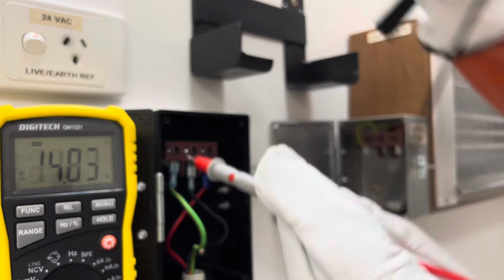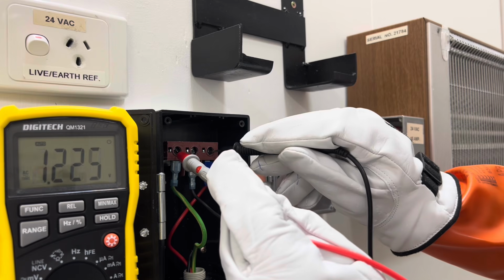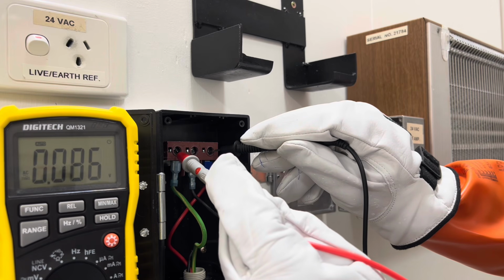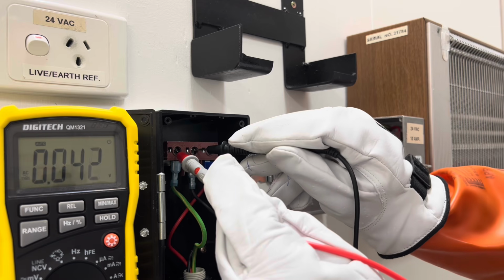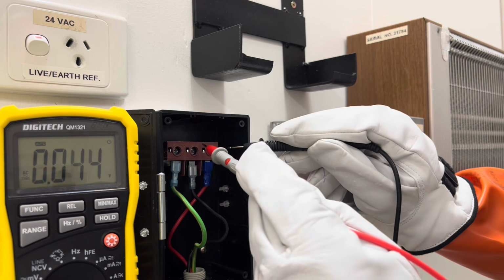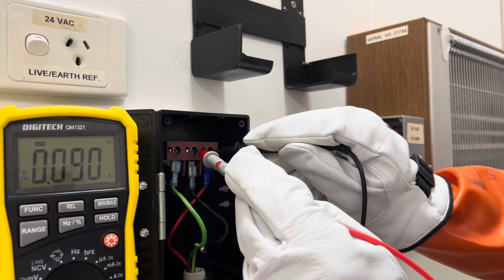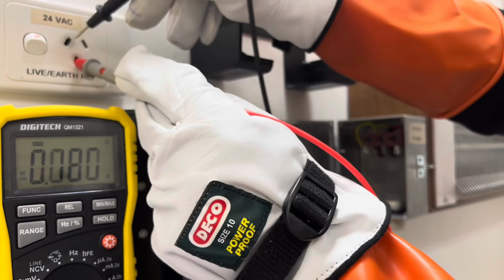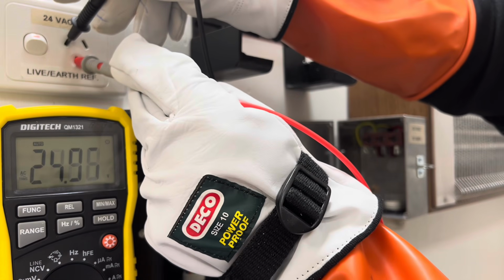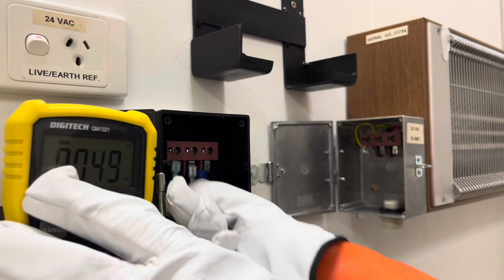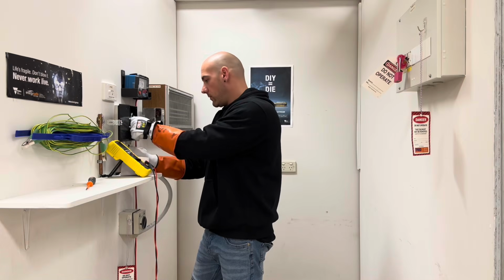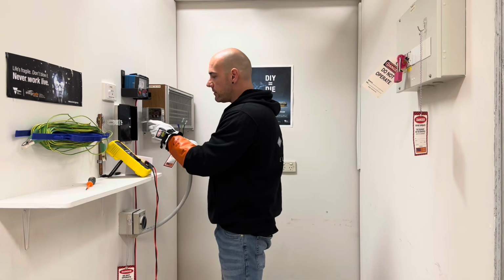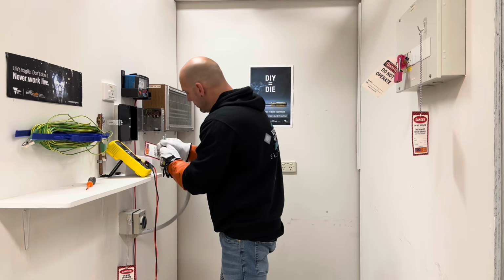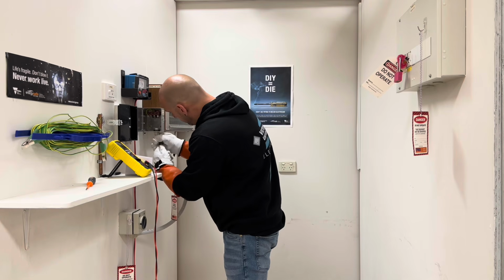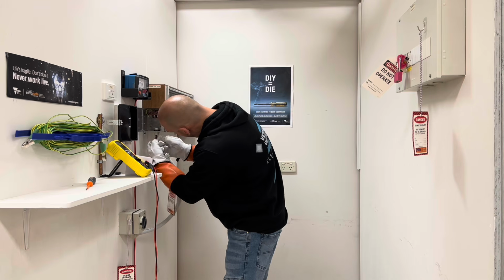And we test between conductors. Earth to active, 0 volts, earth to neutral, 0 volts, and active to neutral, 0 volts. Test our tester. So that is safe to touch. Remove our conductors from the junction box and place them into the terminal block of the heater.